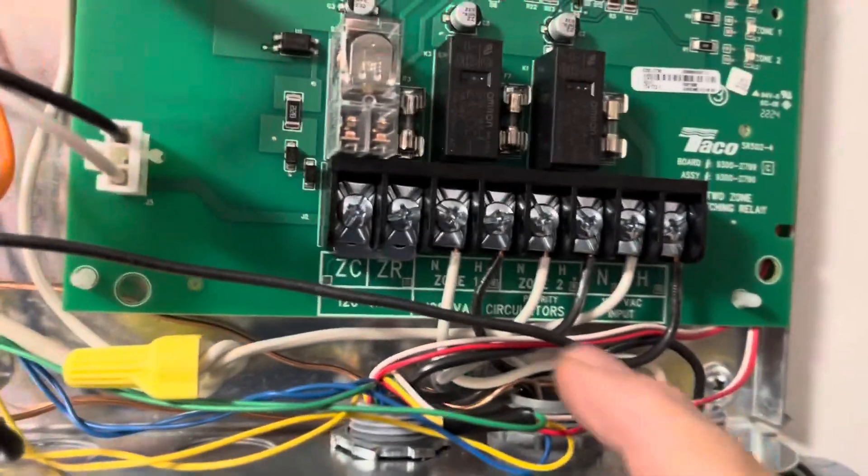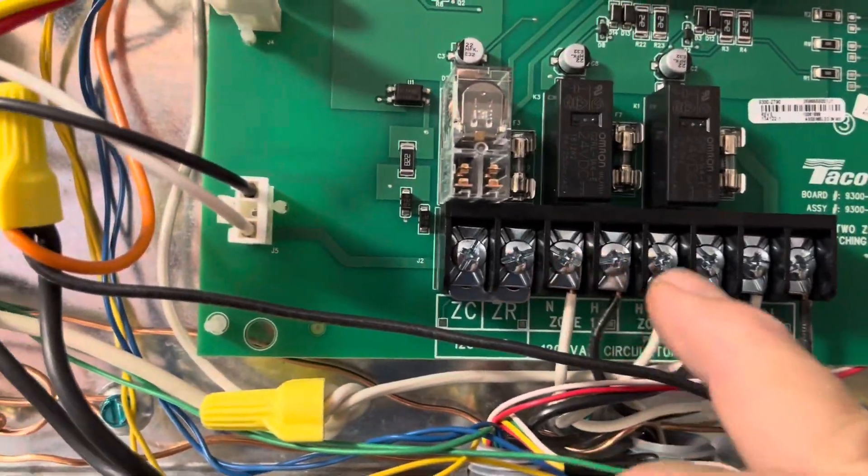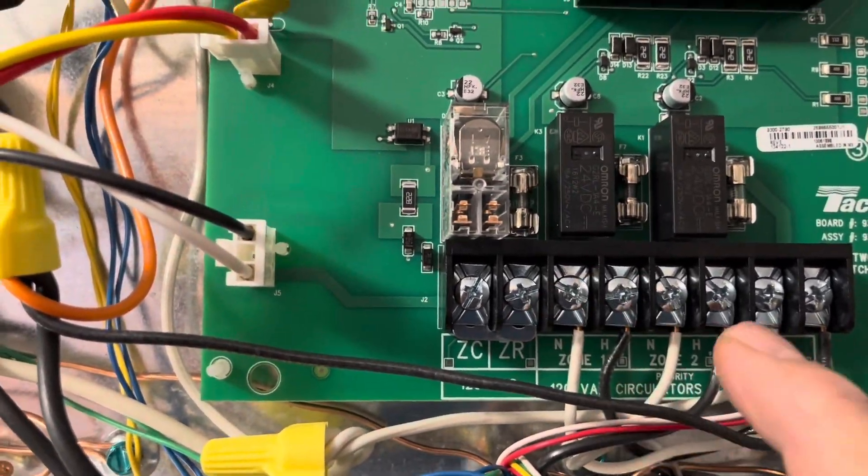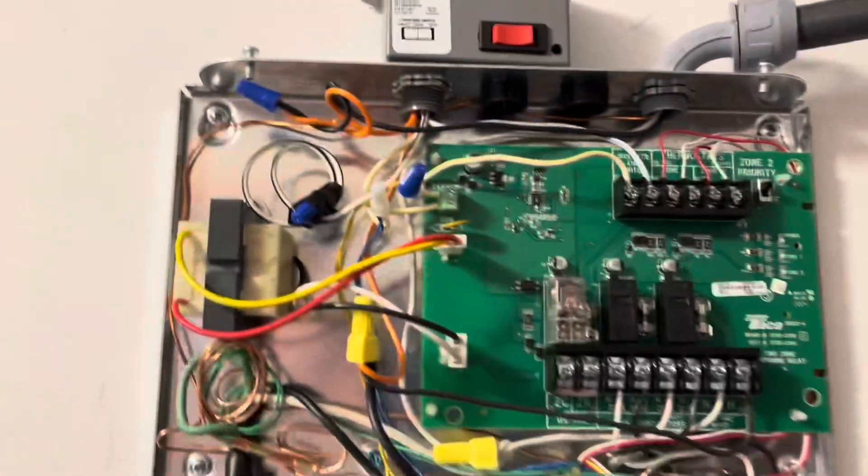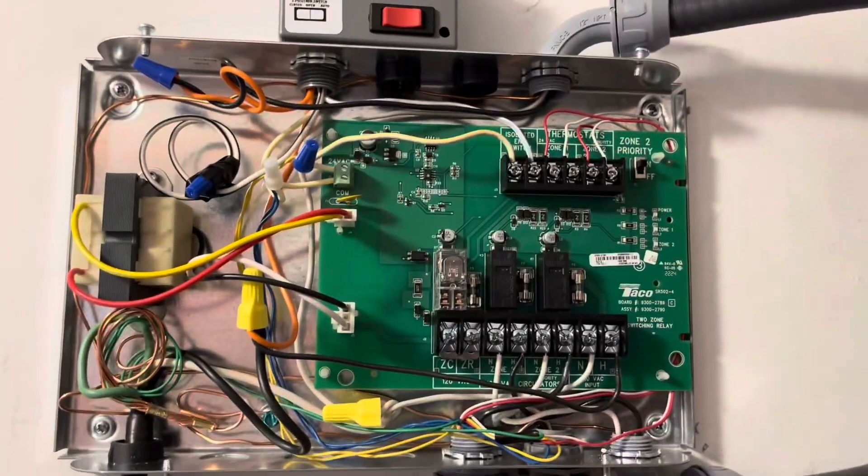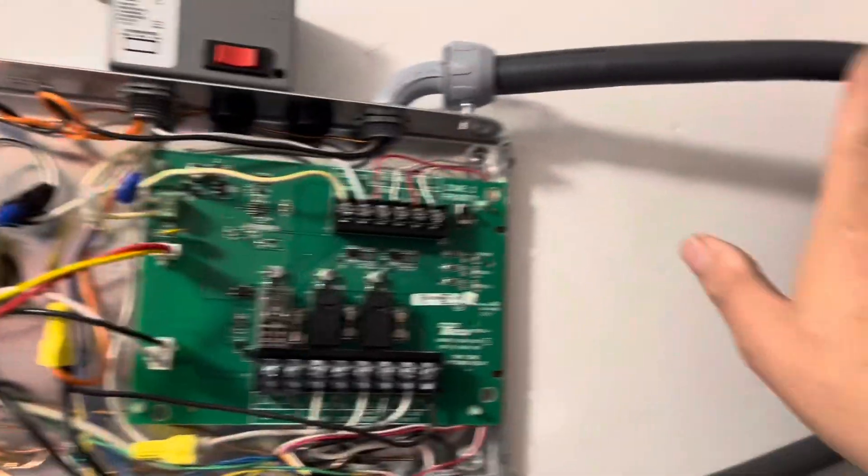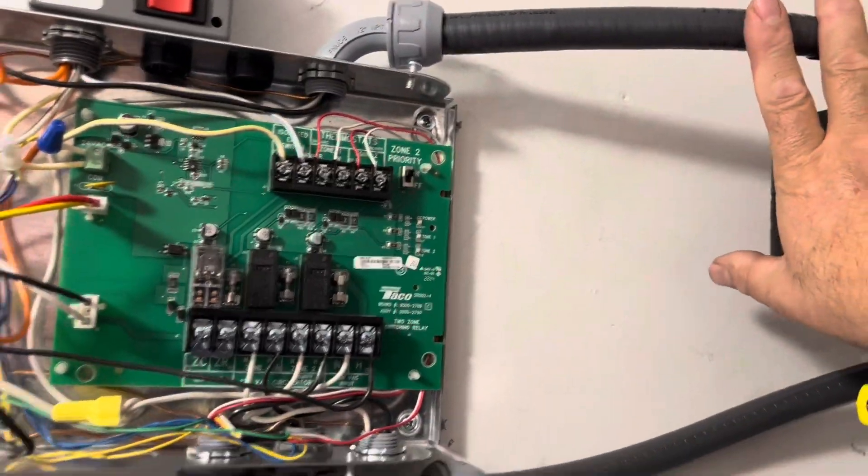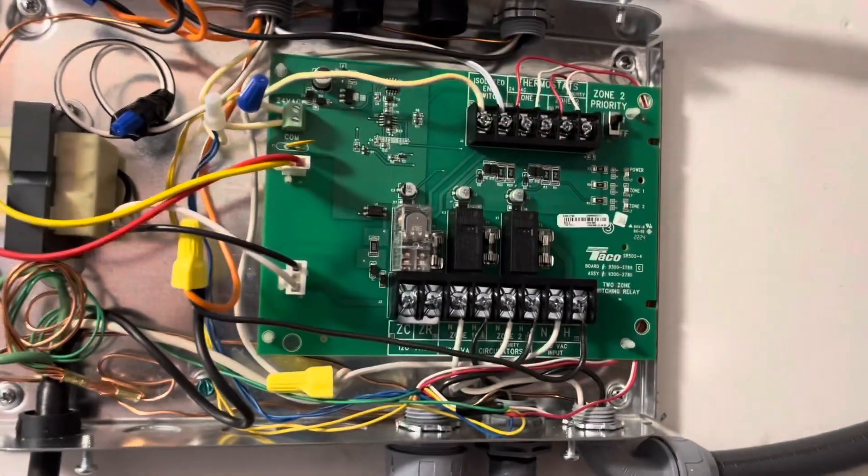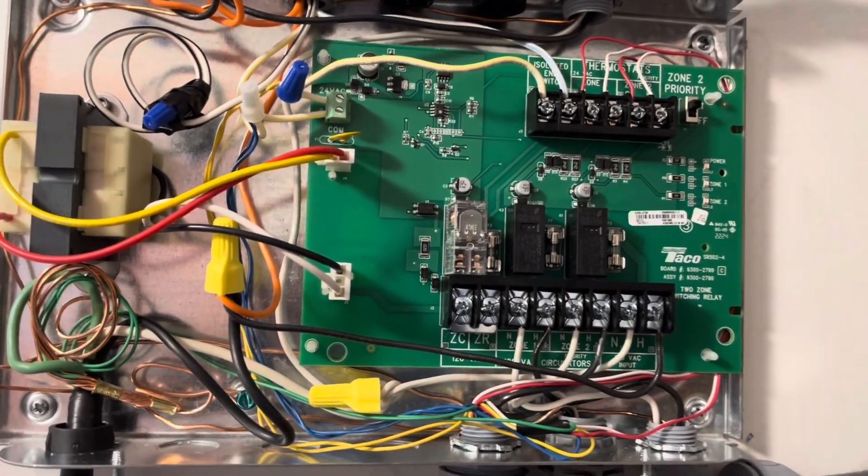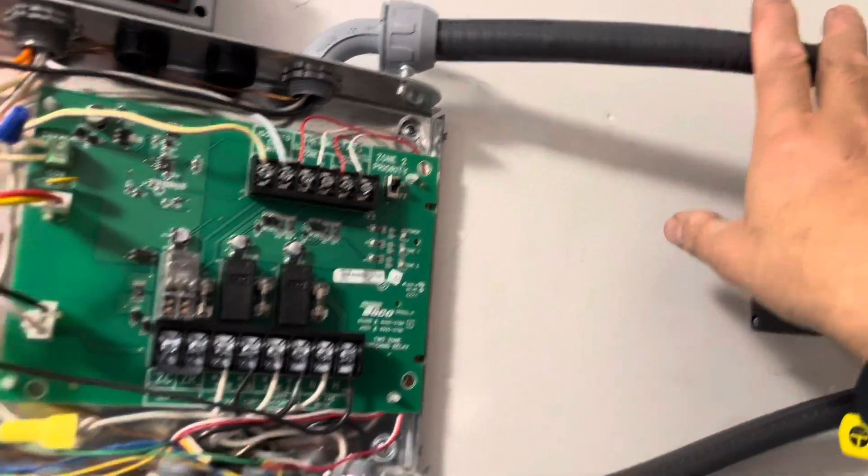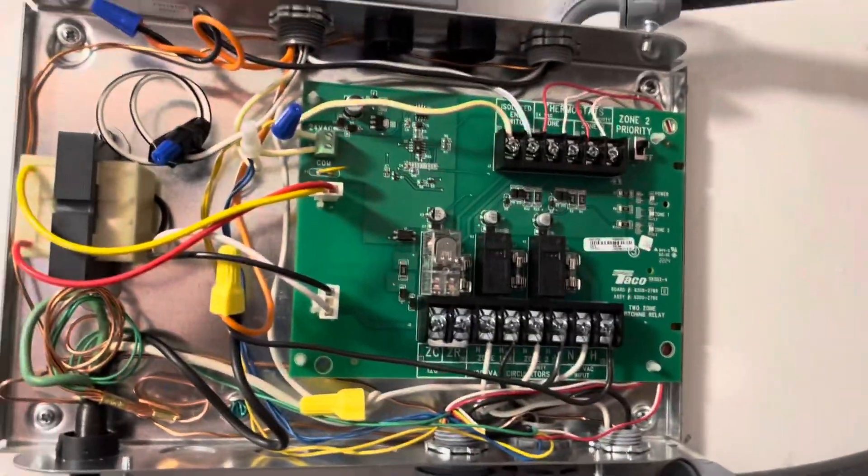There's my zone one pump. It comes all the way back and it feeds here to zone one. So zone one, zone two. And so that's pretty much how it works. When zone one calls for heat, this motor goes on and the zone one motor goes on. When zone two calls for heat, this motor goes on and the zone two motor goes on.